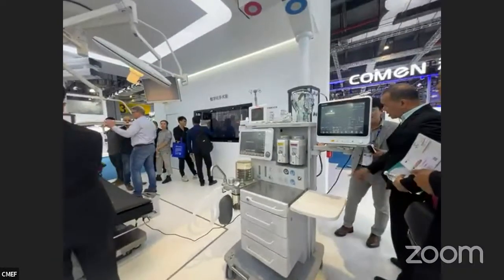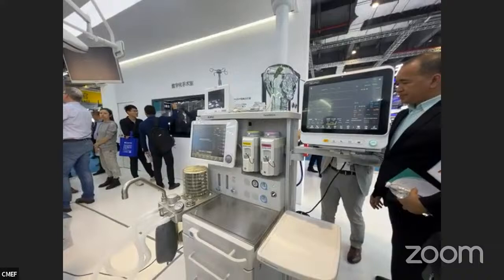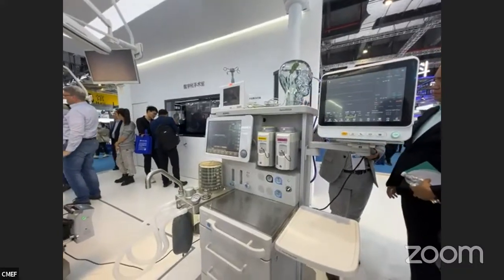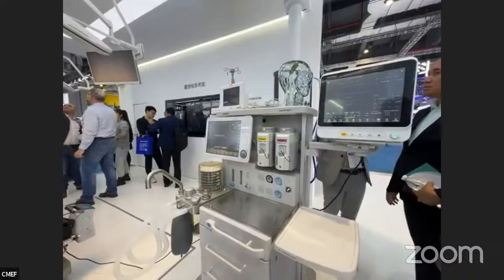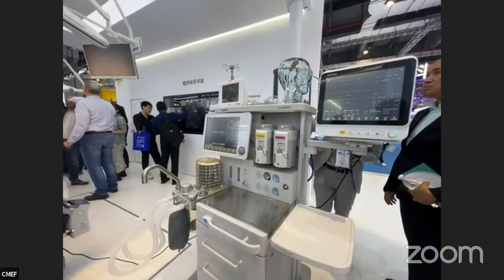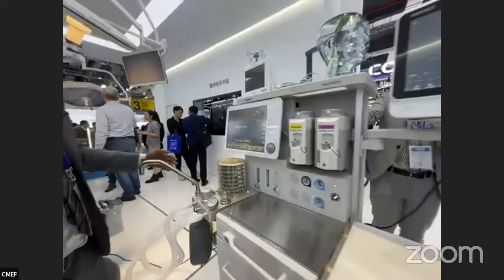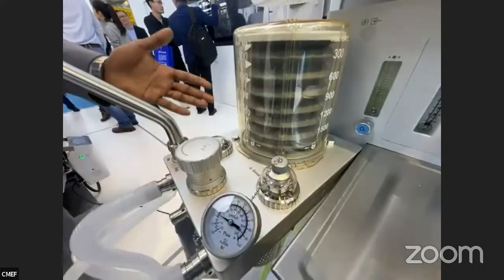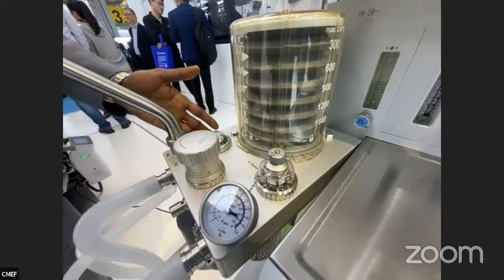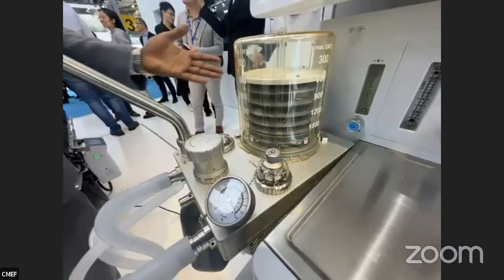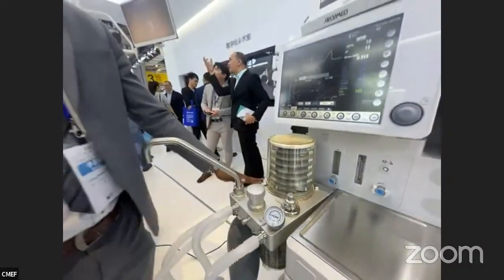integrated OR. So here we have an anesthesia machine. The model is 8800A. This anesthesia machine has a 15-inch touch screen, and the machine also has 2 slots for the vaporizer, an electronic flow meter, and we have drawers, and pressure gauges for the central gas system as well as for the cylinder. If we come to this part, we can see our breathing system. Our breathing system is made of magnesium aluminum alloy, and the whole system can be sterilized. The system is also heated inside, so we can avoid any condensation.